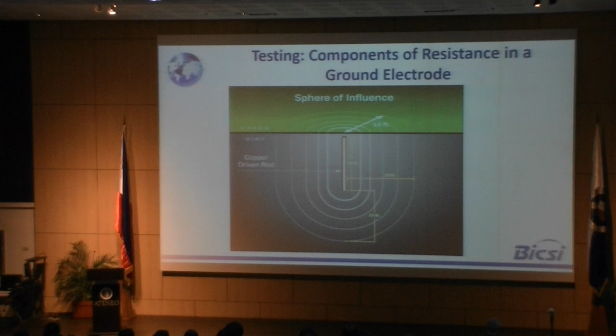There's only one reference. All the standards, there's only one reference to test: that's IEEE 81, the Guide for Measuring Earth Resistance, Ground Impedance, and Earth Surface Potentials of Grounding Systems. How far? Minimum distance for a single electrode is 5 times the length of the rod. Ideal is 10 times the length of the rod.